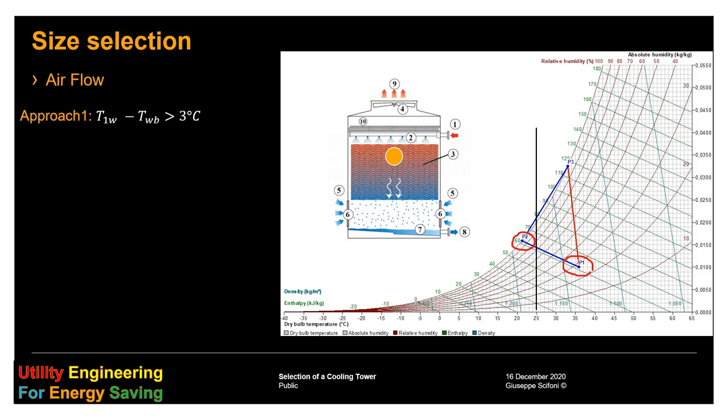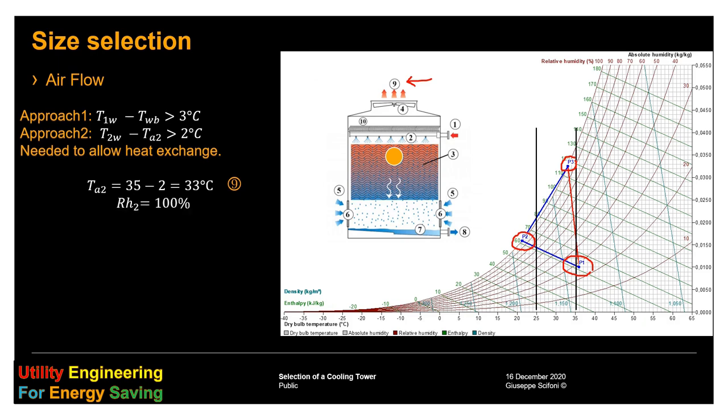The first approach is that the temperature of the leaving water must be at least three degrees higher than the wet bulb, otherwise the heat transfer is not possible. Then we have a second approach saying that the leaving condition of the air, so the point P3, must be two degrees at least lower than the entry temperature of the water, this vertical line and the position nine in this picture. Of course, this condition says that the air is saturated, so 100%.